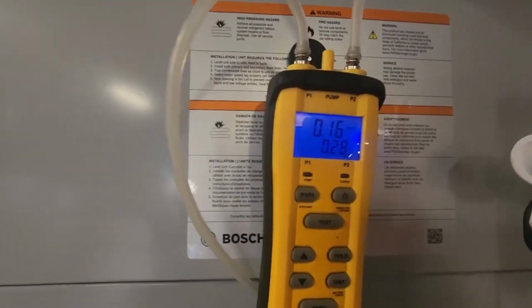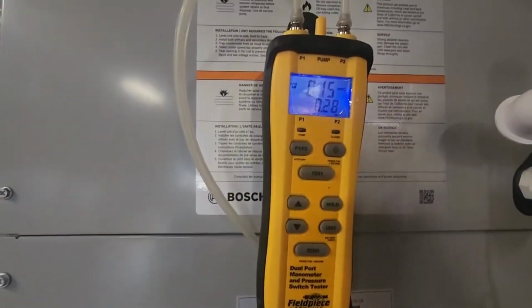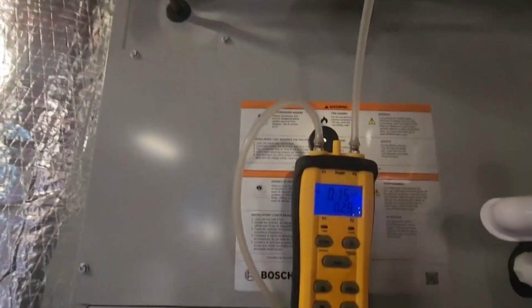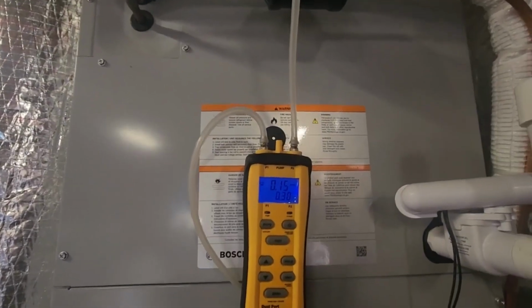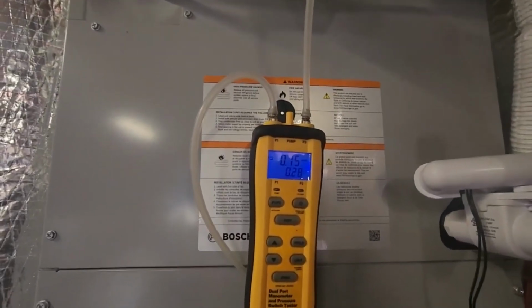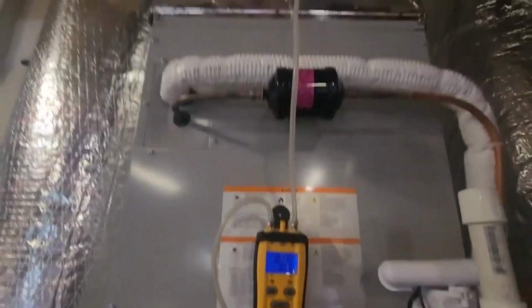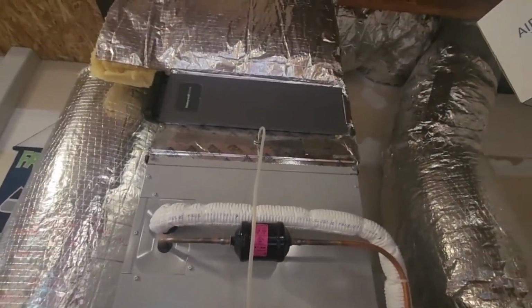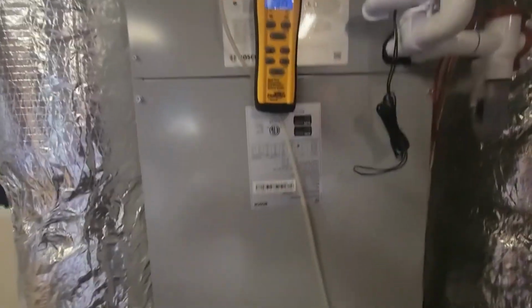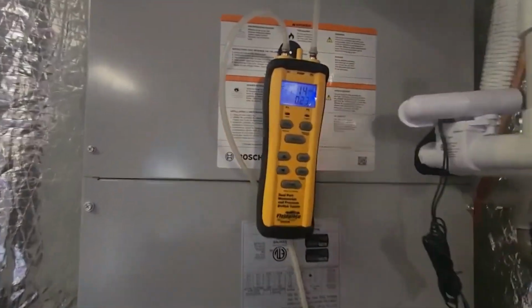But look at those numbers, 0.29 total. I put that filter in, it's about 0.4-ish, so that's pretty awesome. That's why this bypass damper here never opens. So I just wanted to show you how to check these statics, with all the scenarios on a zone system.